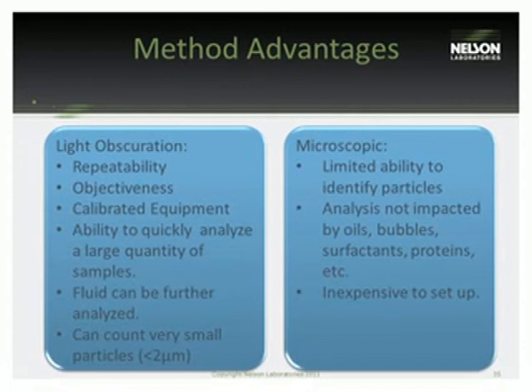Unfortunately, oils and bubbles and these other compounds may also diffract the laser even though they're not true particles, and be detected as particles. That's really the main purpose of the microscopic method nowadays: to confirm counts from the light obscuration method and to use in the case where your sample may not be compatible with the light obscuration method. But even in cases where you may know that these compounds exist on your device or your sample, it's still a good idea to have that sample run using the light obscuration method to see if those compounds will cause a significant interference. And if they do cause interference, to have justification for going to the microscopic method.